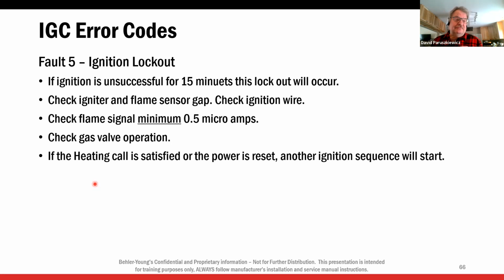Why did it lock out? Well, did it light? That's the easiest one. The crossover tubes are dirty. So if you look at the burner, you've got the crossover tubes. The first burner's lighting, but it's not carrying it across to the flame sensor. Is the flame sensor bad? Is the flame sensor wire bad? Check the gap in the flame sensor. Is there any rust hanging down on the sensor? Flame signal minimum 0.5 microamps. Now we're going to talk about checking that in a second. But if we have less than 0.5 microamps of flame signal, that won't prove a flame either. So we need to check that.